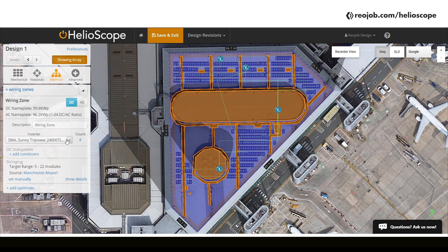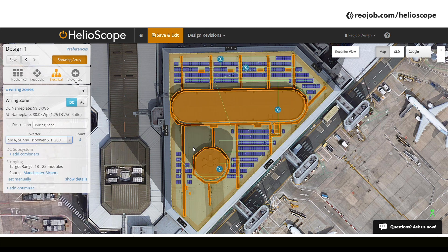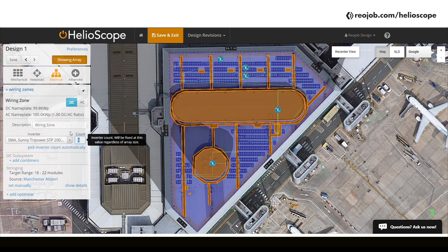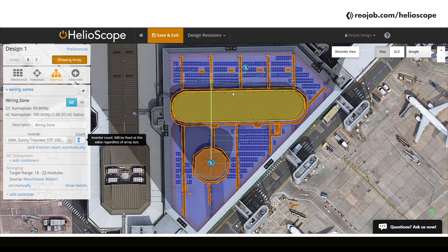The last step in this video is the electrical design. The electrical design lets us choose an inverter and our preferred electrical configuration. We'll start by typing in the brand name. The software will then calculate the number of inverters required and gives you a fairly accurate count. To optimize it further, you can edit the value. Let's click and drag the inverter to a desired location where we plan to install them physically. Note that the position of the inverter greatly affects the cable losses, which you can view in the final report and adjust if required.